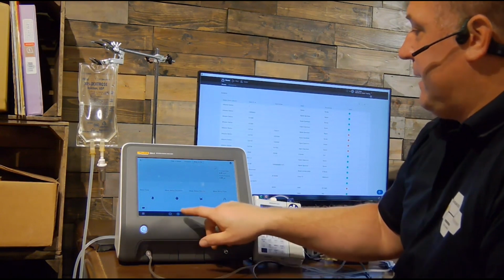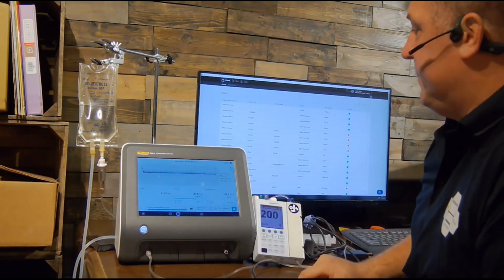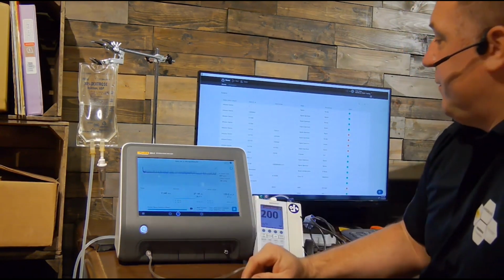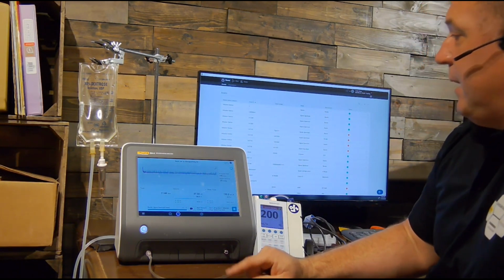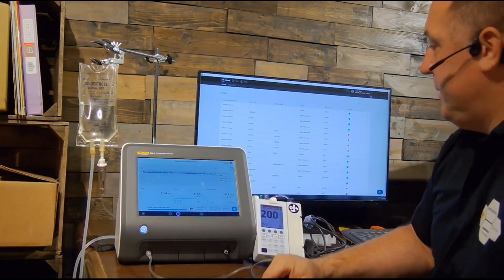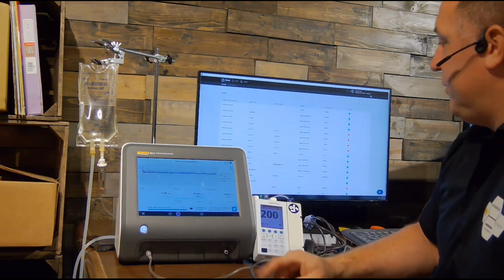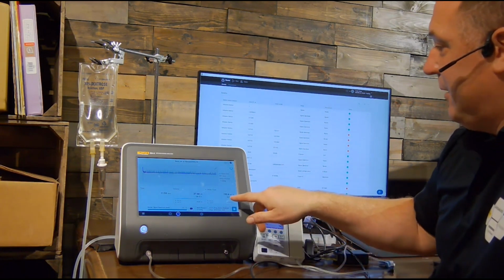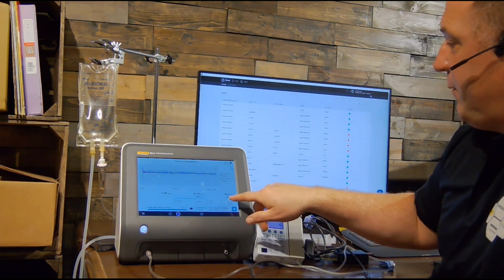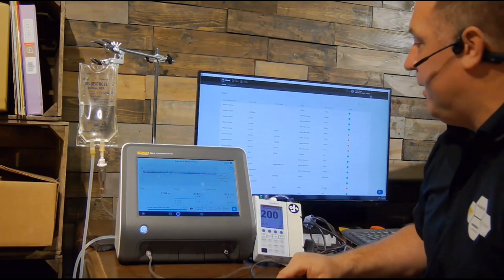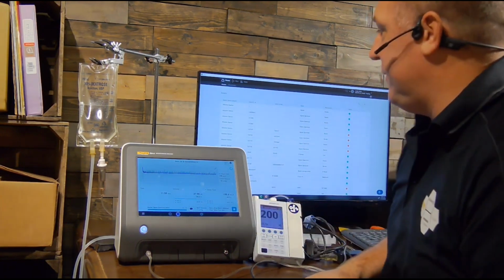All right, let's check back on our pump. We're 11 minutes and 43 seconds in, at 37.32 milliliters, and my mean flow is still around 190. We're right against that limit at 4.9, with our limit at 5.0. We'll see how this pump finishes out.